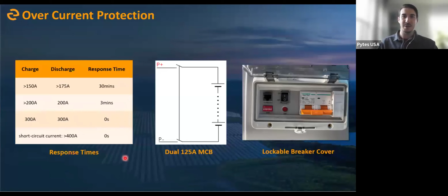And then just a quick shot of our surge ratings on the battery. 150 amps is the max continuous discharge. Between 150 and 175, you can do that for 30 minutes. And then a 200 amp rated discharge or above 200 amps of charge, it'll sustain that for 3 minutes. Once you get to 300 amps, then it's essentially a 0-second response time, and that's when the BMS disconnects.